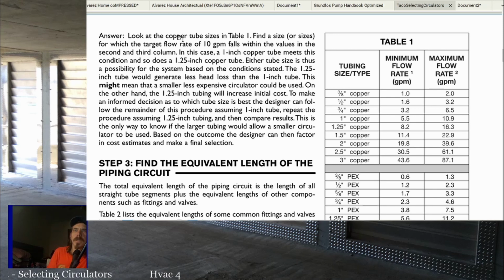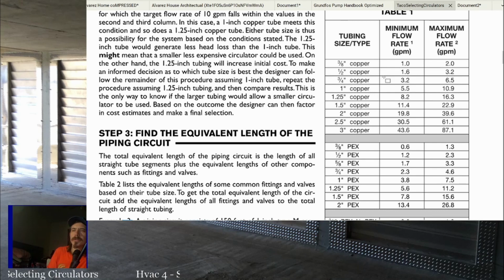So look at the tube sizes and find a size for which the target flow rate of 10 GPM falls within the values of the second and third columns. In this case, 1-inch copper tube meets this condition, and so does 1.25-inch copper tube. So we said we needed 10 GPM, right? So 10 GPM is between the minimum and the maximum flow rate right here. 1-inch copper is between 5.5 and 10.9 GPM. So that's our range of flow that we can have through copper. And then right here, 1.25 is 8.2 to 16.3 GPM.